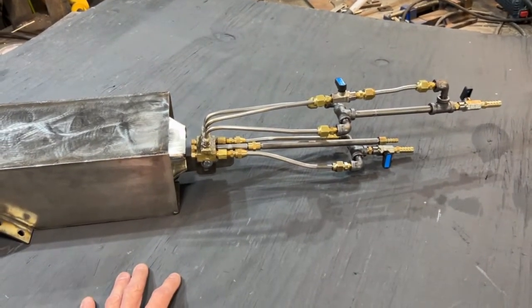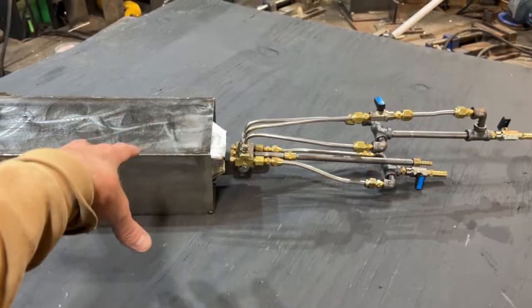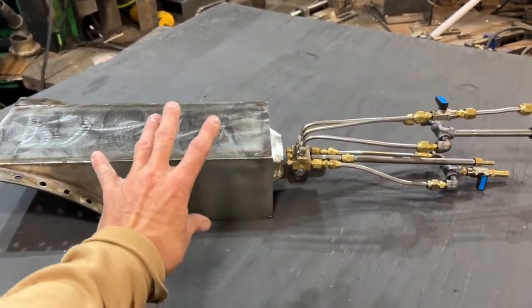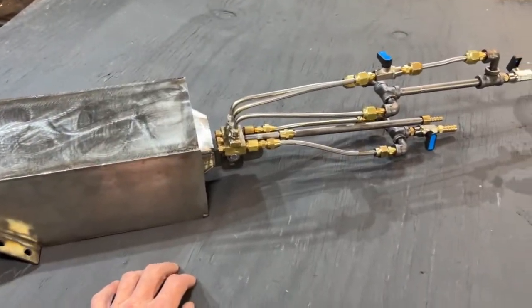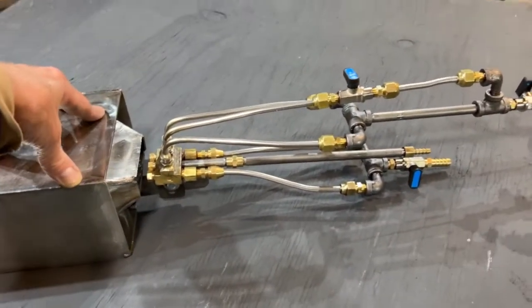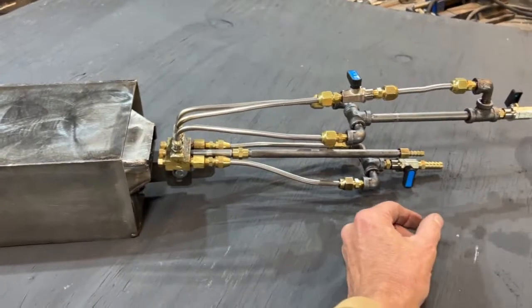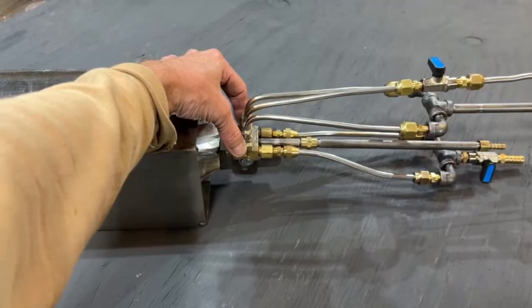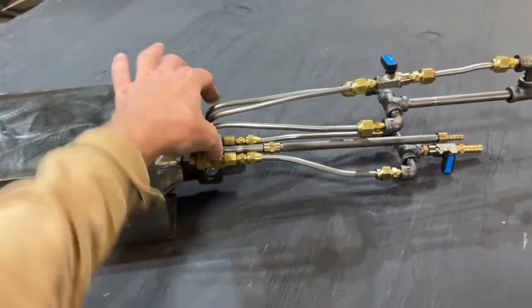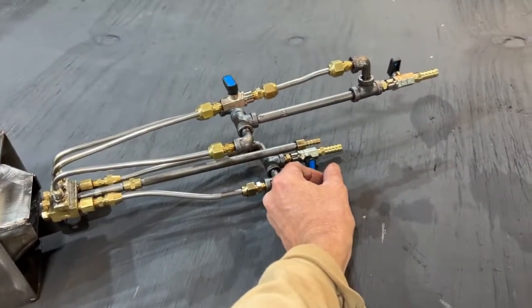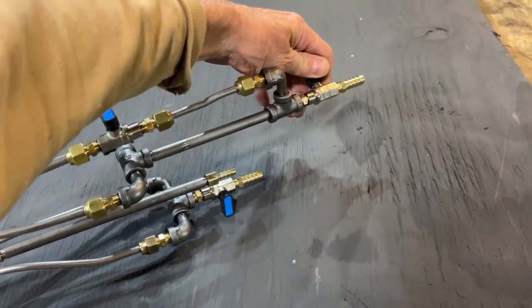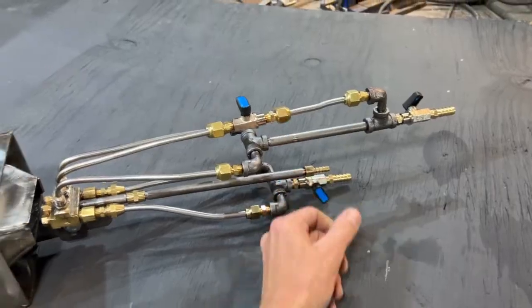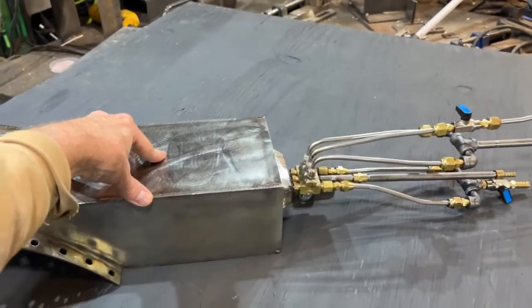I'm not totally sure that would eliminate all of them, but at some point I'm pretty sure you can burn all that stuff up. To control this thing, you would start off by starting the two outer burners first. The way you would do that is to turn on the air just a little bit, a very small amount of air and a moderate amount of fuel to get the burners going.